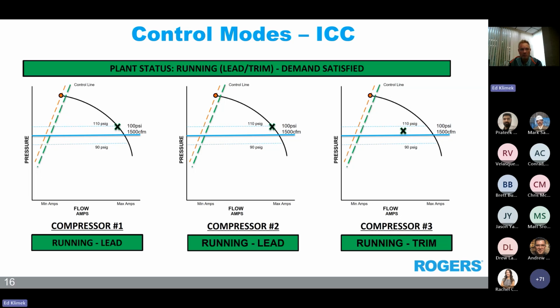So now I'm going to demonstrate more of a load sharing. With the demand satisfied, you'll see an example of how all compressors throttled to the same inlet position to equally share the required load. All inlet or guide vanes would position together at the same time and work together.